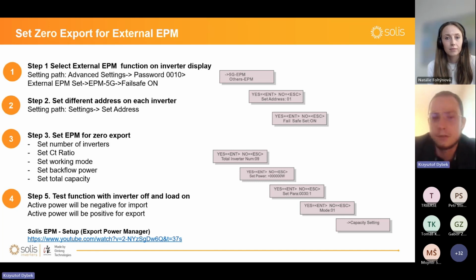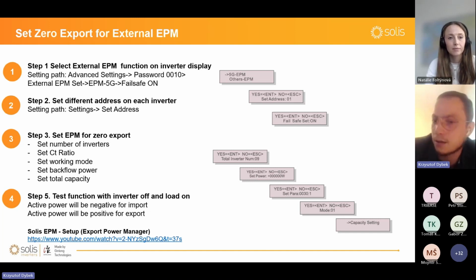Minus 100 watts or 0. 0 is enough. And set total capacity. So add the power of all your inverters. So if you have, for example, a 30 kilowatt inverter and a 110 kilowatt inverter, your capacity will be 140 with three zeros at the end, because this value is in watts, not in kilowatts.